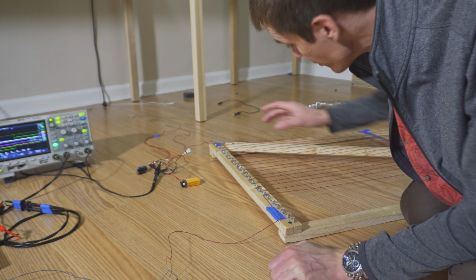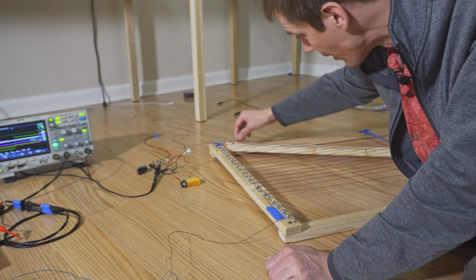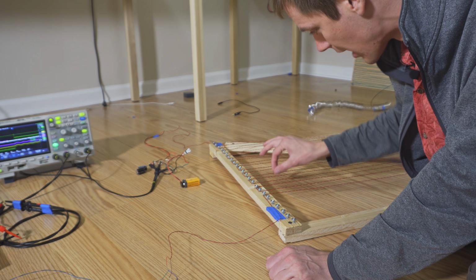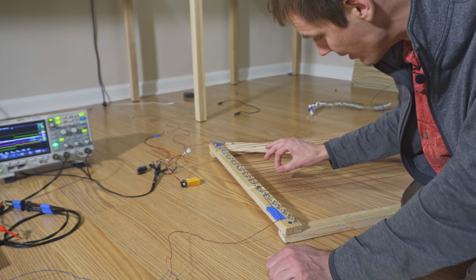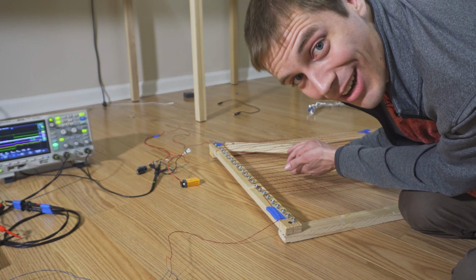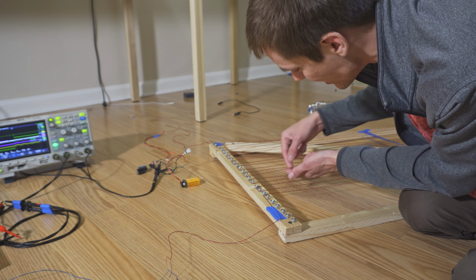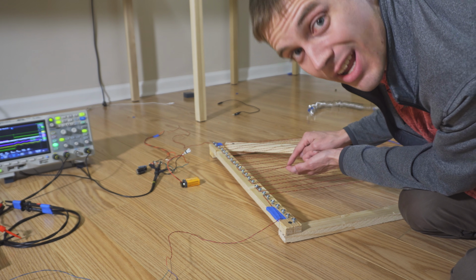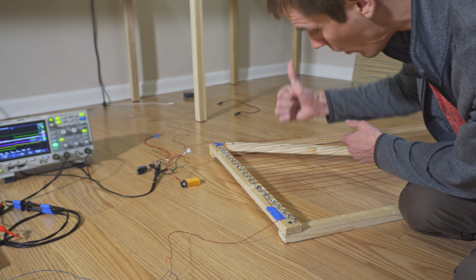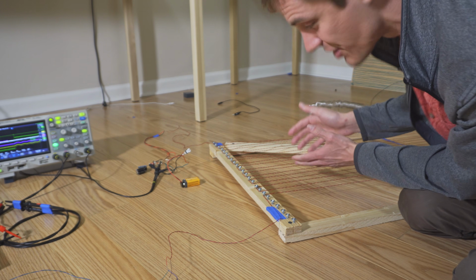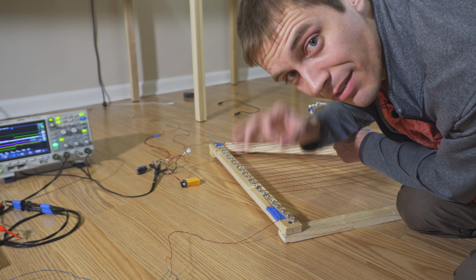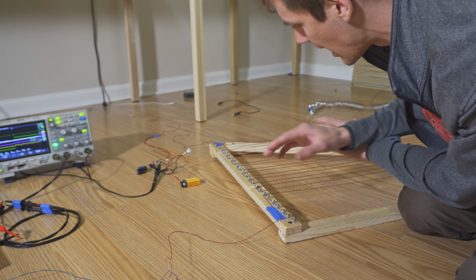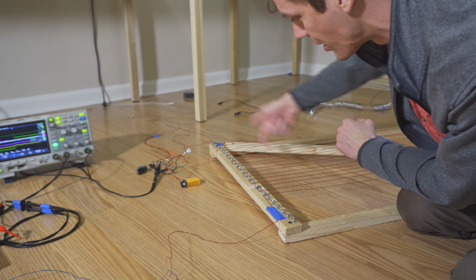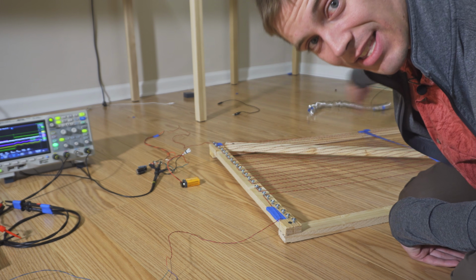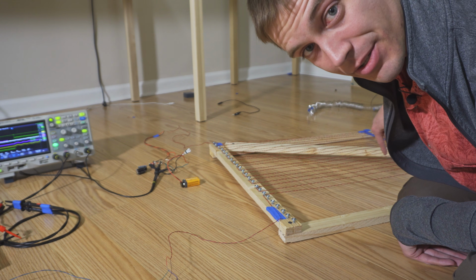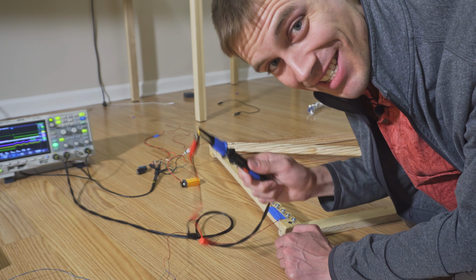When you flip the switch and flow current into this wire, it creates an electric field that may affect the wire next to it. This is actually two wires, so if I take the difference in voltage between them, it should be zero. Even if both wires undergo a massive change in potential, if the difference between them stays zero, I've eliminated the crosstalk effects and can see only the signal traveling the full distance. When I put probes here, that's exactly what's going on.